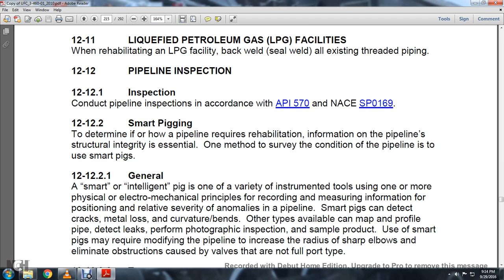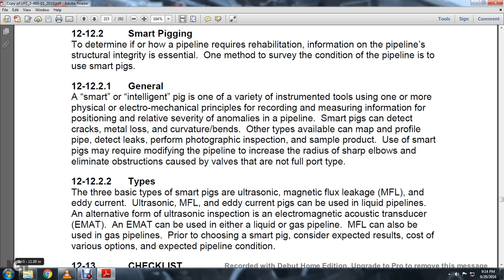Pipeline smart pigs can detect cracks, metal loss, curvature, and bends. Other types are available that can map the profile, detect leaks, perform photographic inspection, and sample product. Using smart pigs may require modifying the pipe, increasing the radius of sharp elbows, and eliminating obstructions caused by valves that are not full port type.